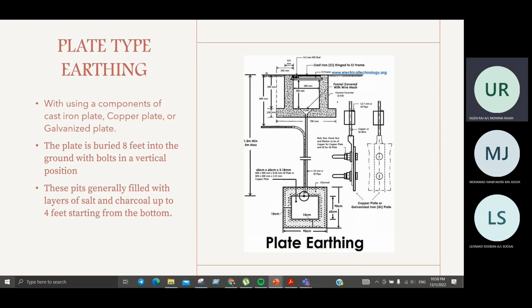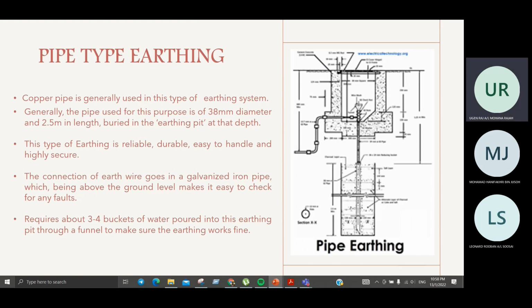Okay, so next is pipe type earthing. Generally we use a copper pipe for this type of earthing system. Generally the pipe used for this method has a diameter of 38 mm and a length of 2.5 meters. It will be buried in the earthing pit at a great depth in the soil. This type of earthing is reliable, durable, easy to handle, and highly secure. The connection of the earth wire goes in a galvanized iron pipe, which, being above the ground level, makes it easy to check for any fault. This requires about 3 to 4 buckets of water poured into the earthing pit through a funnel to make sure the earthing works fine.